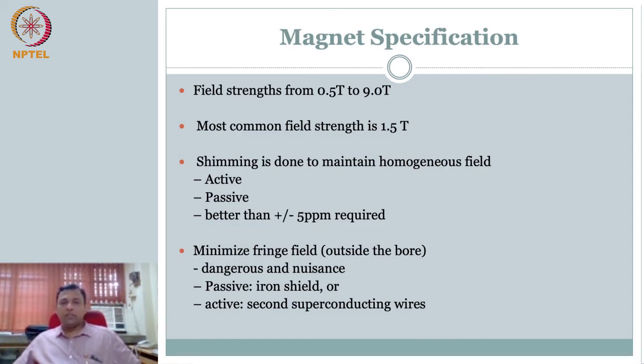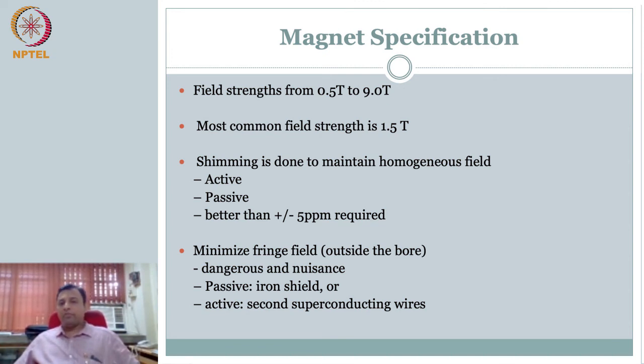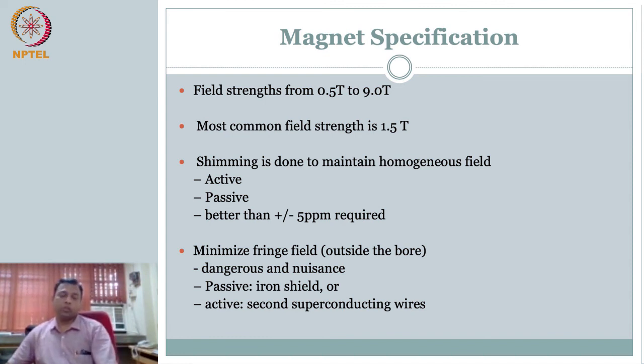What are the typical specifications you get with superconducting magnets? Field strengths from 0.5 Tesla to 9 Tesla, with 1.5 Tesla being most common. With shimming — which gives you a homogeneous field — you get better than plus or minus 5 parts per million. There are several shimming techniques: passive shimming and active shimming. You also get minimized fringe field. These are the specifications typically available with superconducting magnets, which is why they are popularly used.